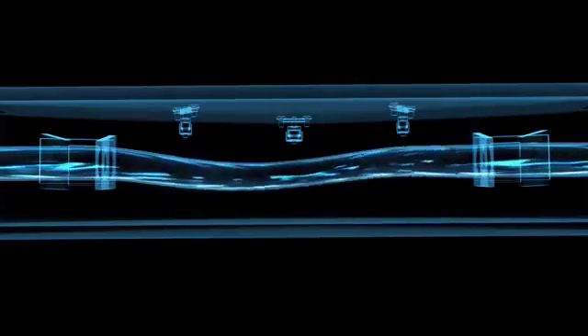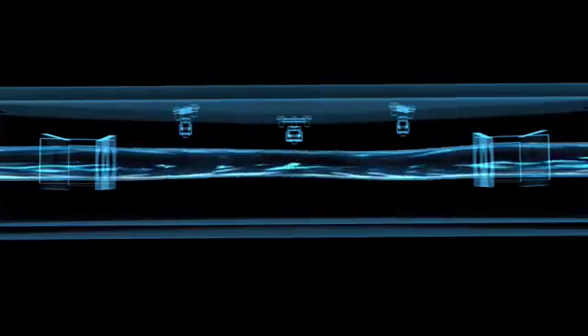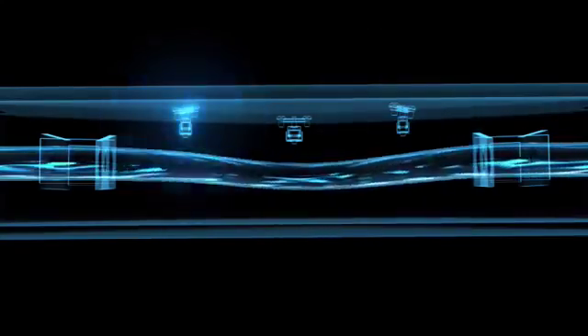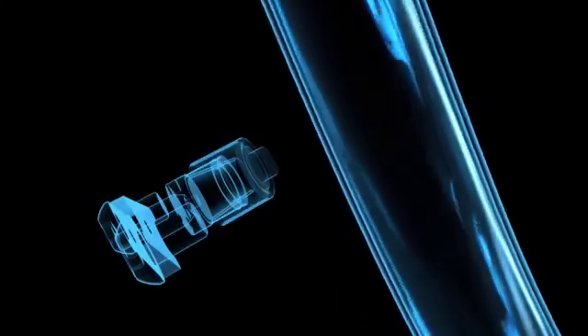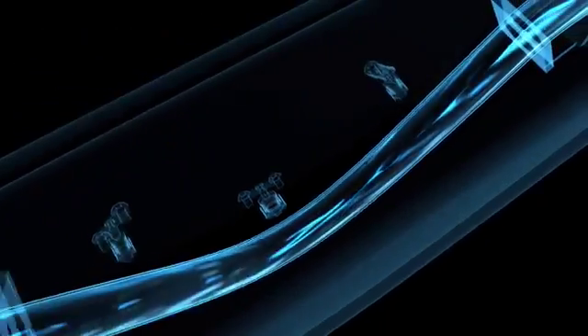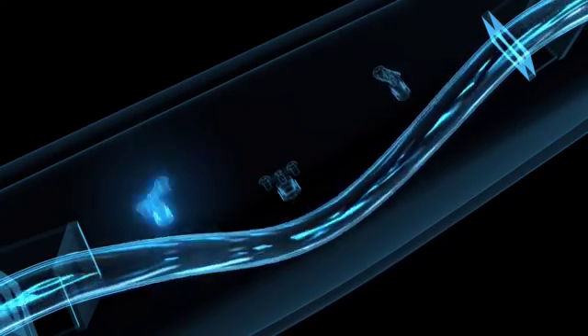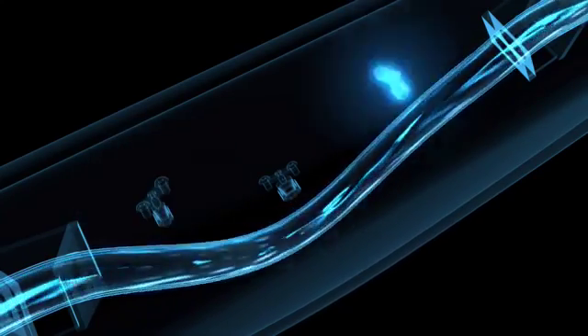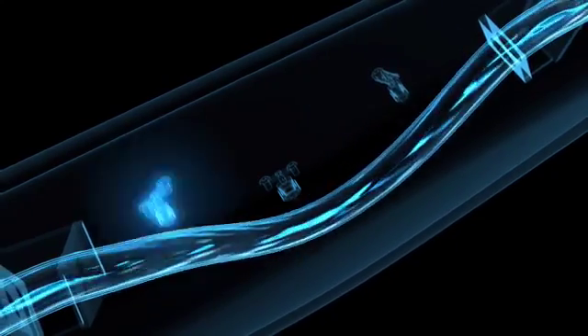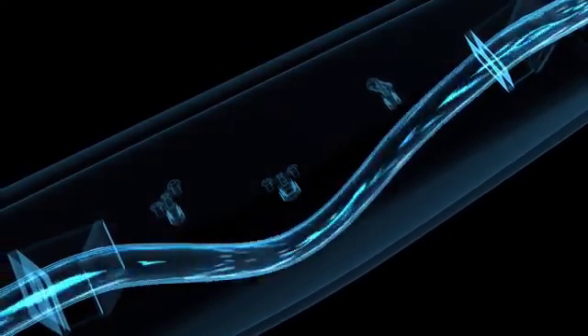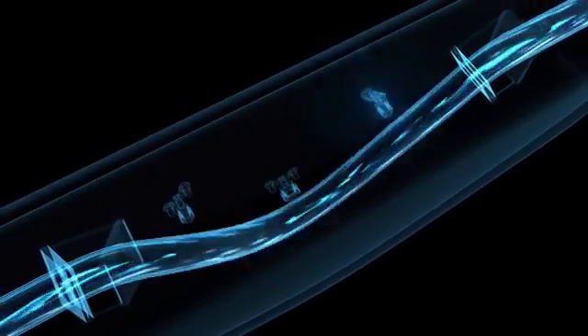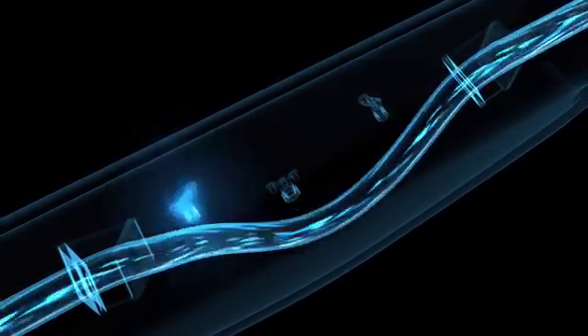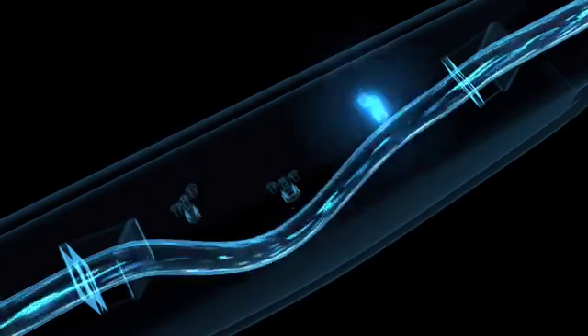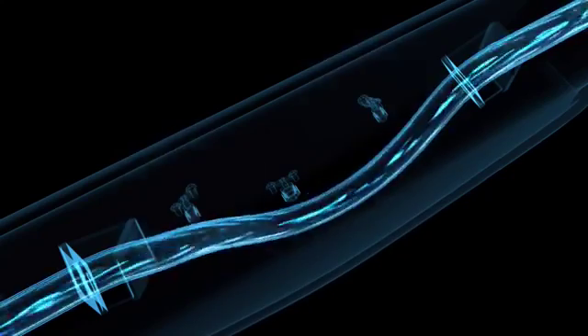Now, due to the Coriolis effect, the inlet and outlet sections of the tube oscillate in different directions at the same time. The highly sensitive sensors pick up this change in the tube oscillation in terms of time and space. This is known as the phase shift, and is a direct measure of how much liquid or gas is currently flowing through the pipe. The higher the flow velocity, and thus the total flow, the greater the deflection of the oscillating measuring tube. The application of the Coriolis measuring principle doesn't stop here.